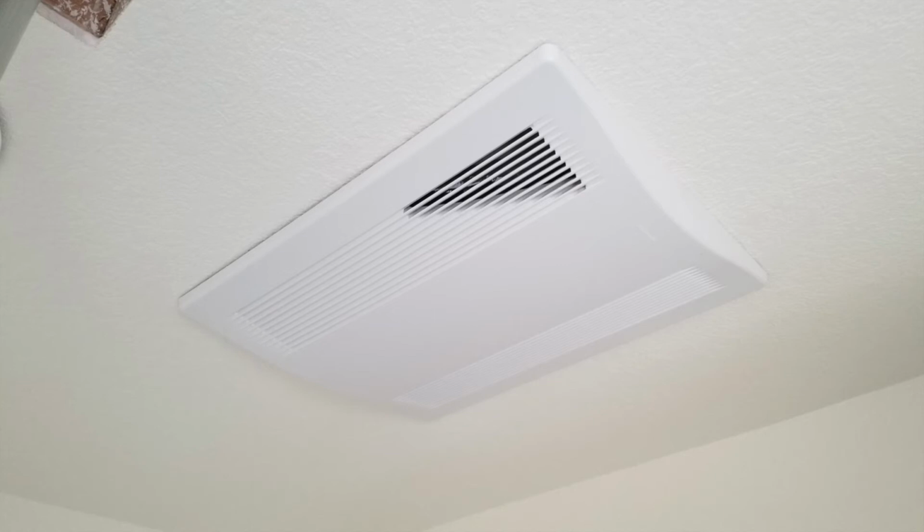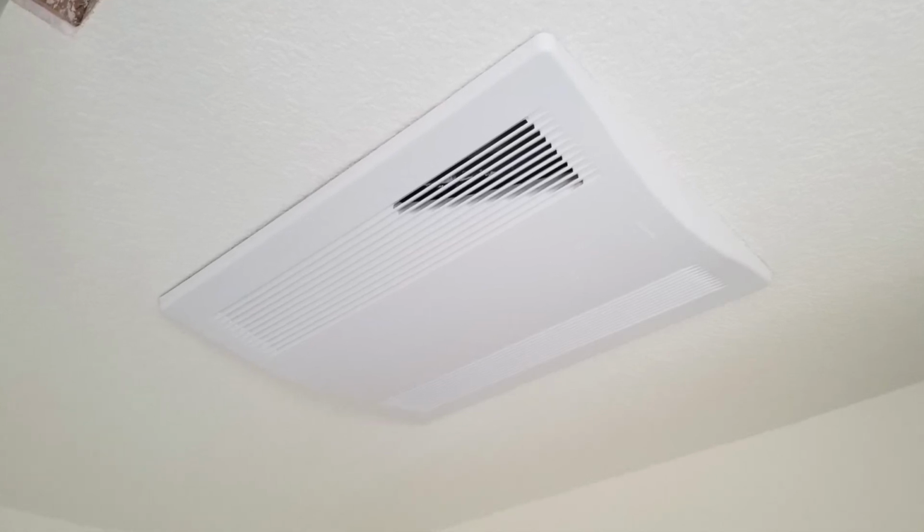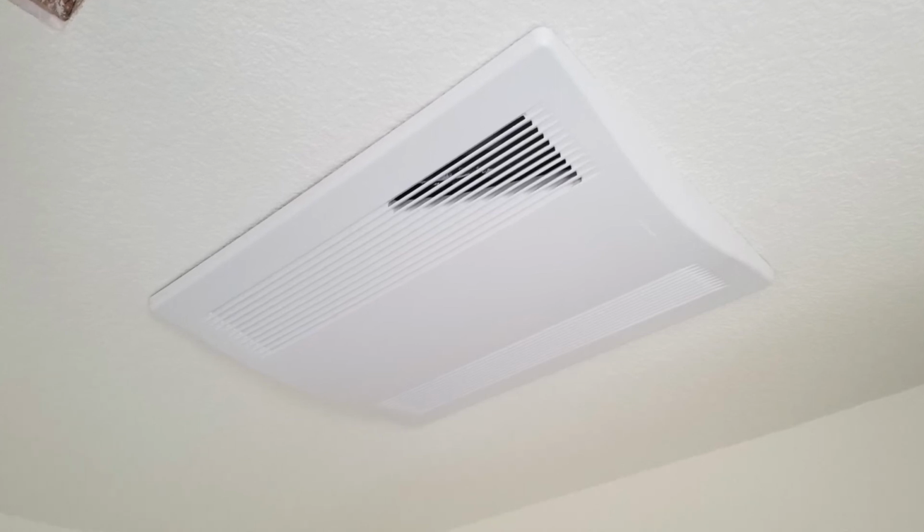Instead of your larger HRV or ERV cabinet, you could elect to install something maybe a little simpler, but still also will check the box, a spot ERV, which is kind of a glorified bath fan. Instead of a bath fan, which just does dedicated exhaust, a spot ERV is like that, except it also has an intake line. So it will do that kind of balanced mech vent. And a spot ERV is going to be way cheaper than a full ERV or HRV cabinet install.